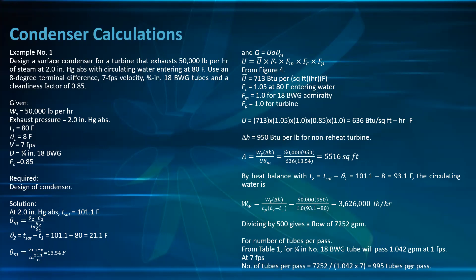Q = U·A·θ_m. To find U = Ū × F_T × F_M × F_C × F_P: from figure 4 at 7 ft/s for 3/4 inch tube, Ū = 713; F_T = 1.05 at 80°F; F_M = 1.0 for 18 BWG admiralty metal; F_P = 1.0 for turbine.